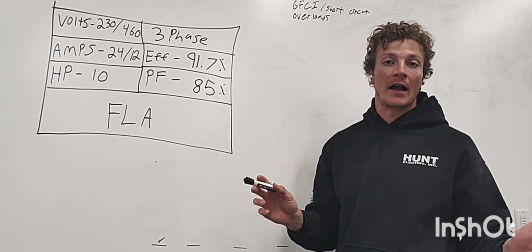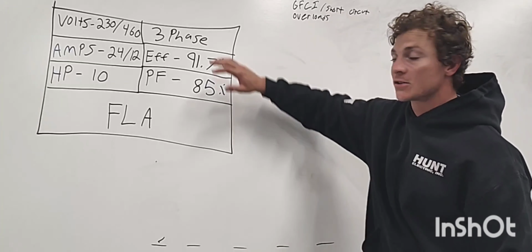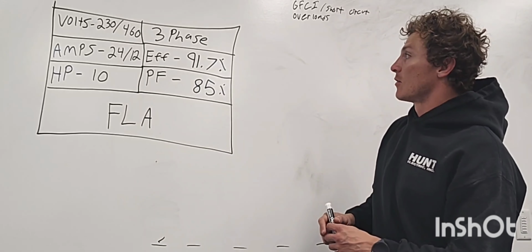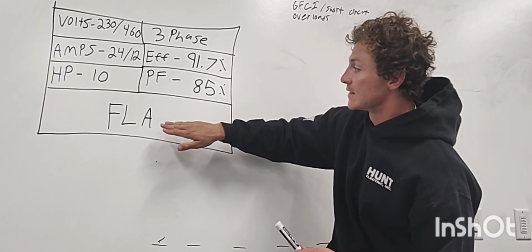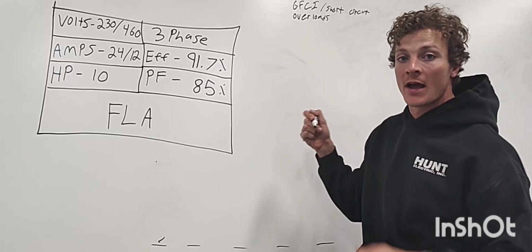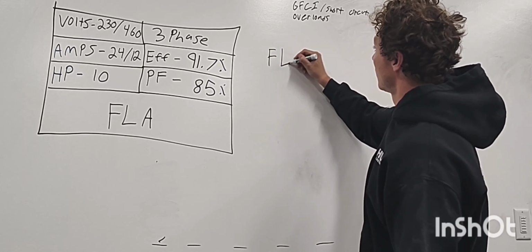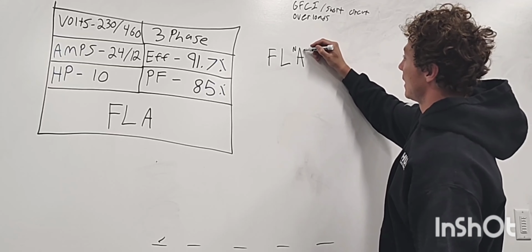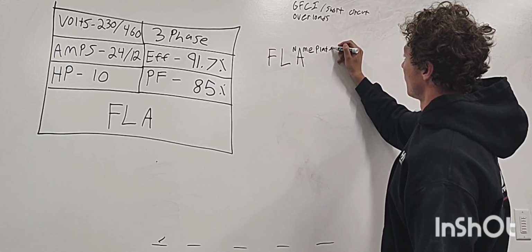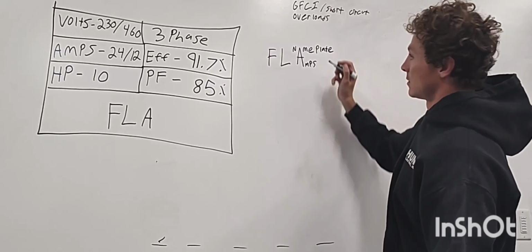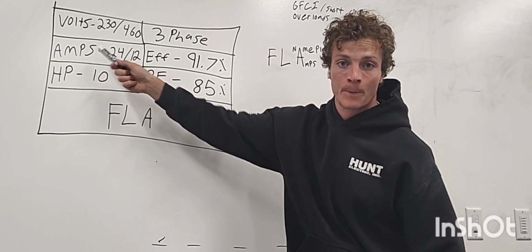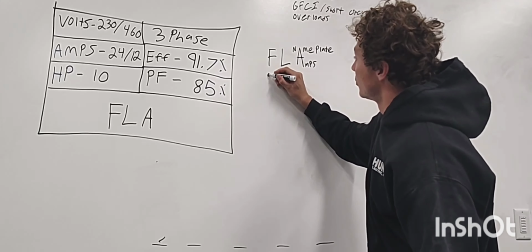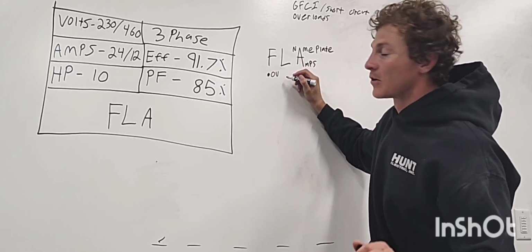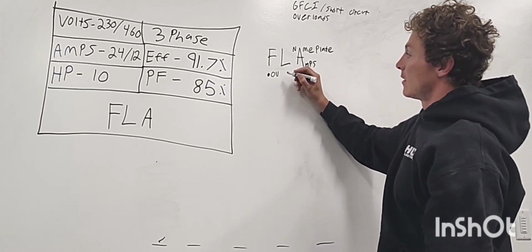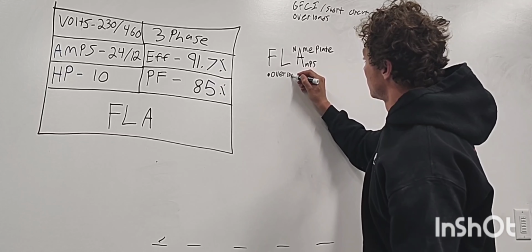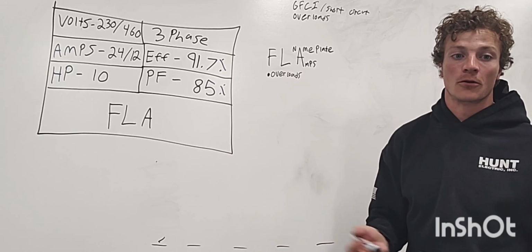So, here's a little trick that I use to remember what is what. So right here is our nameplate that we had on the motor. Going from this, we just have to remember that this is the full load amps, the FLA. I remember that by this: FLA is the nameplate, and it's the full load amps. So that amperage is found right here. What do you use the FLA for? You use the FLA, the nameplate, to size your overloads. That's essentially it for the full load amperage.